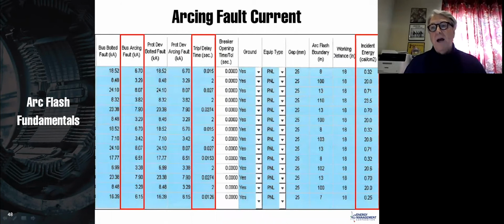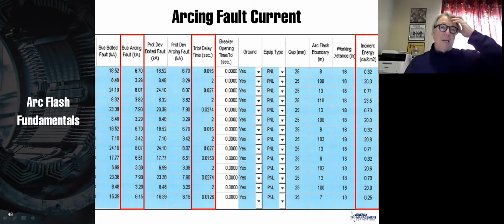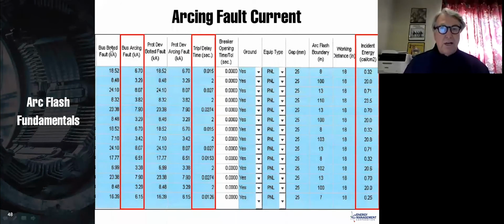Now, here is an output from an arc fault study. You'll notice that it has the bus bolted fault. It has the arcing fault. It has the time delay. And over here, we have the incident energy. And then, of course, there's a number of other things as well.